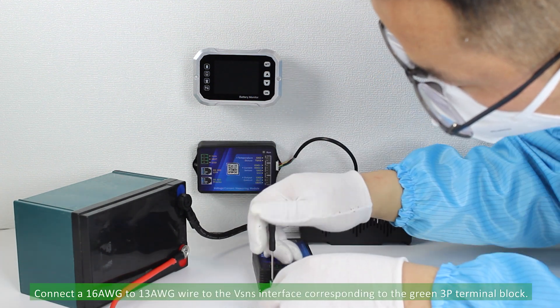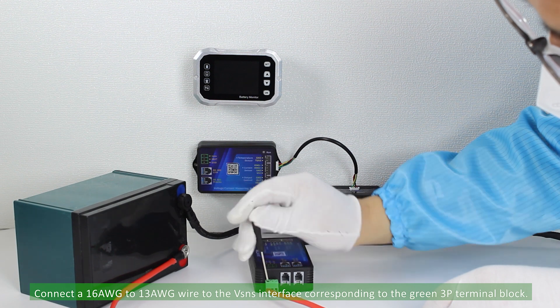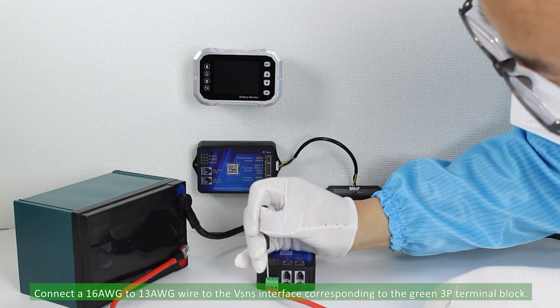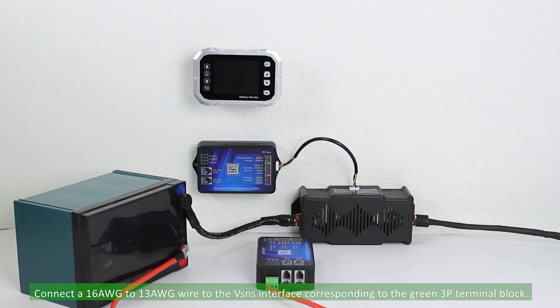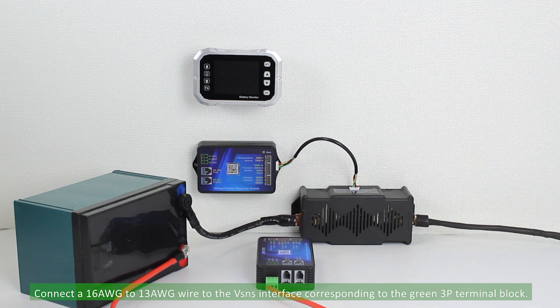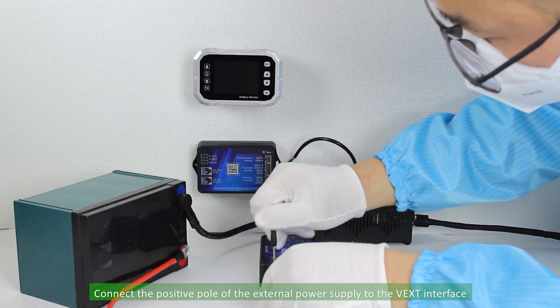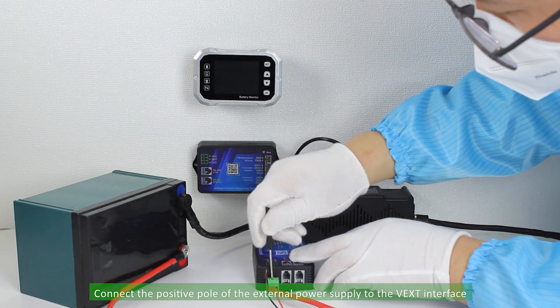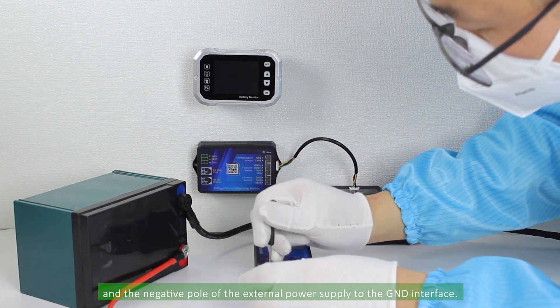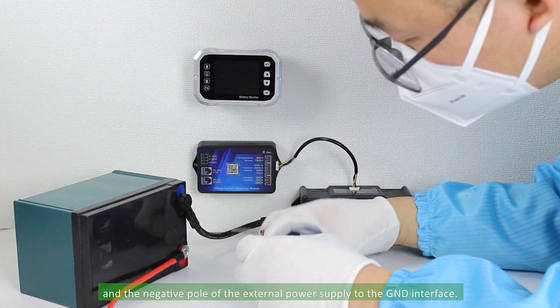Connect a 16 AWG to 13 AWG wire to the VSNS interface corresponding to the green 3P terminal block. Connect the positive pole of the external power supply to the VEXT interface, and the negative pole to the GND interface.